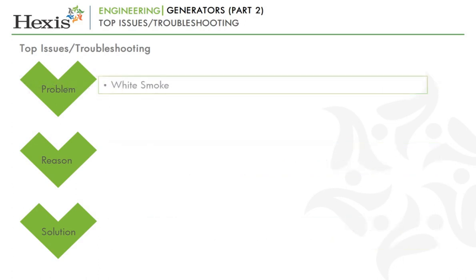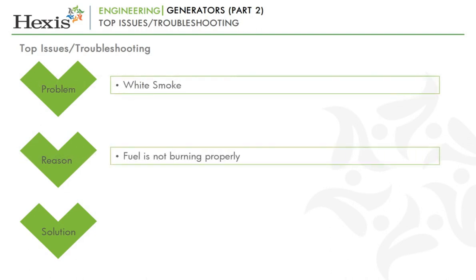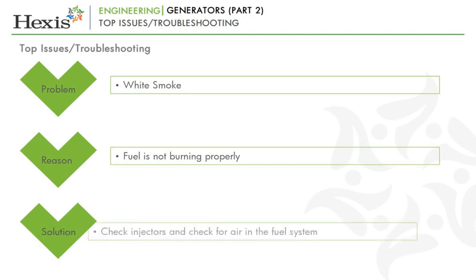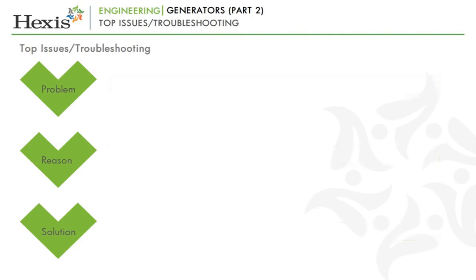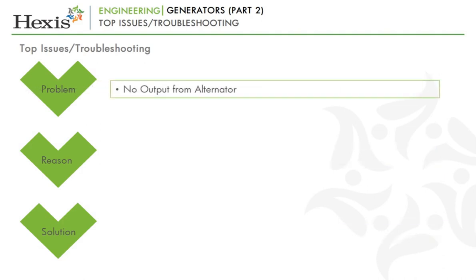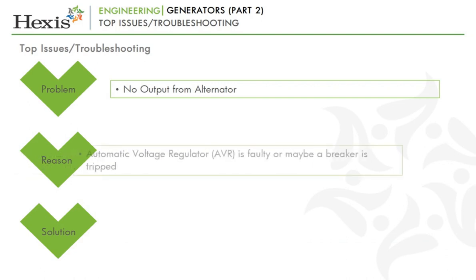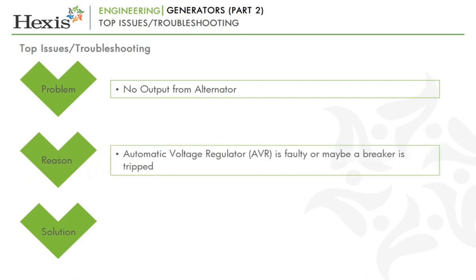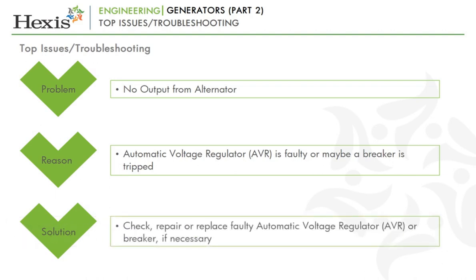Problem: white smoke from the diesel generator. Reason: white smoke is indicative of fuel not burning properly. Solution: check injectors and check for air in the fuel system. Problem: no output from alternator. Reason: this could be because the automatic voltage regulator AVR is faulty or maybe a breaker is tripped. Solution: check and repair or replace faulty automatic voltage regulator, that is AVR, or breaker if required.